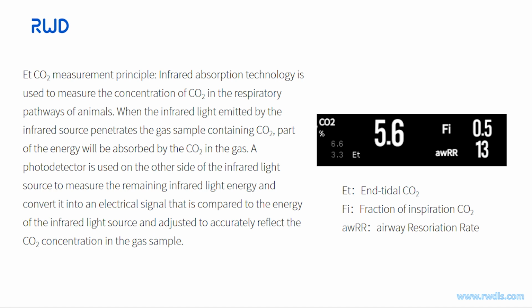A photodetector is used on the other side of the infrared light source to measure the remaining infrared light energy and convert it into an electrical signal that is compared to the energy of the infrared light source and adjusted to accurately reflect the carbon dioxide concentration in the gas sample.